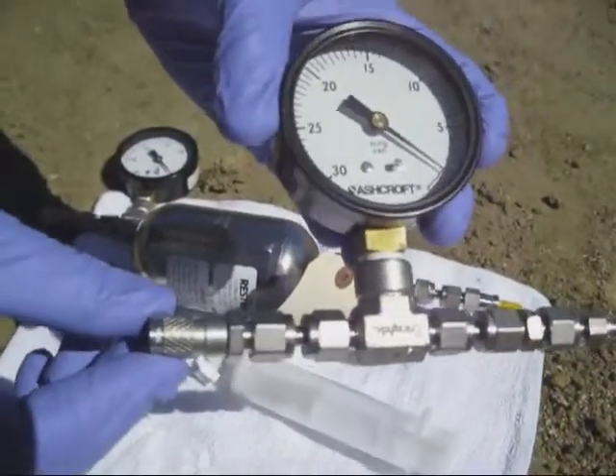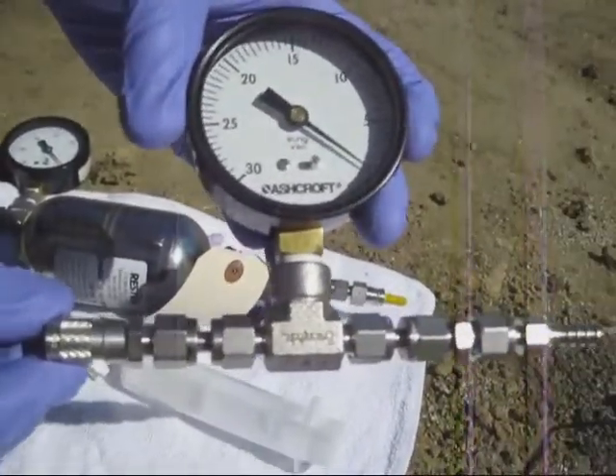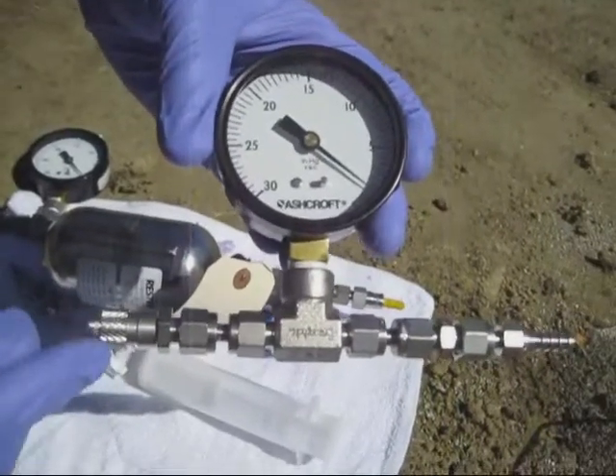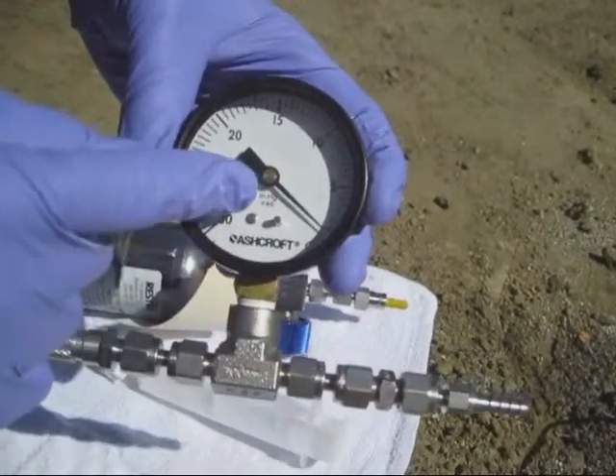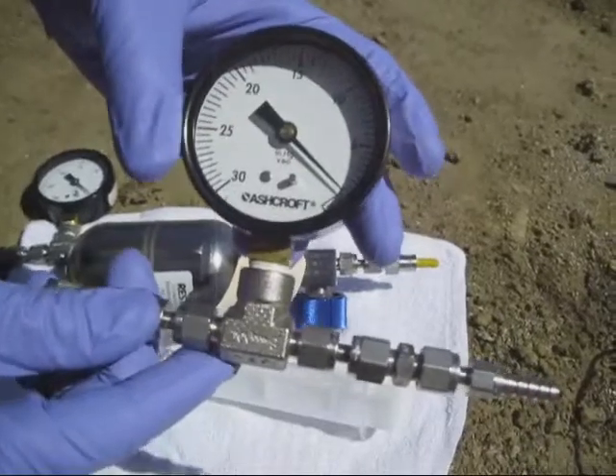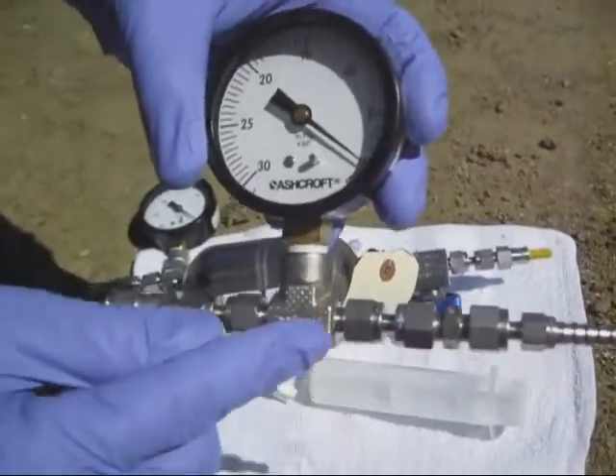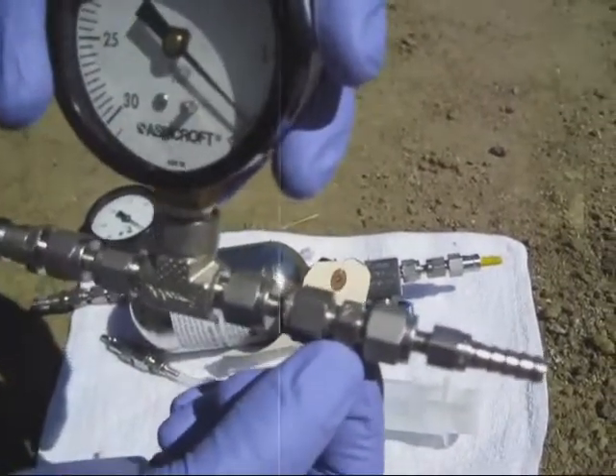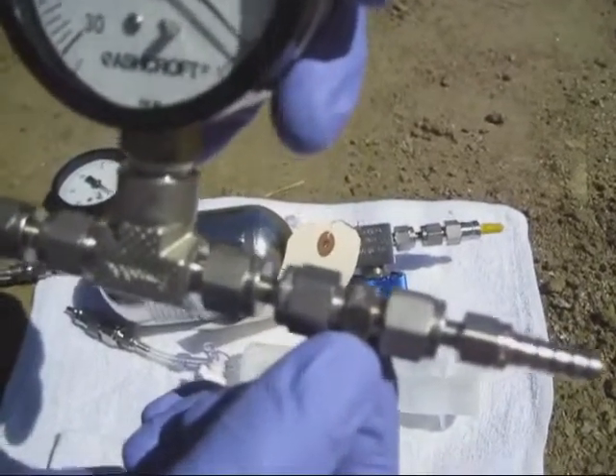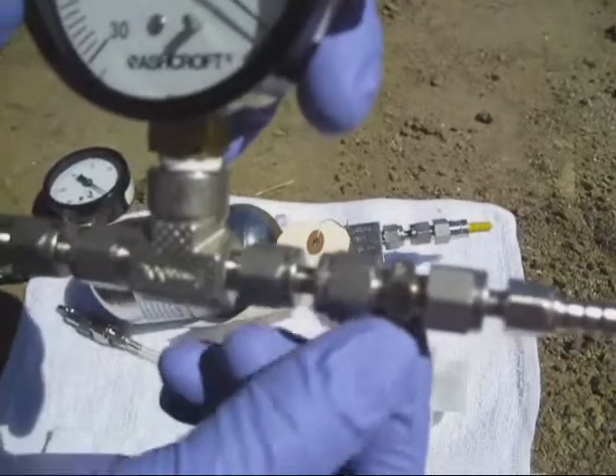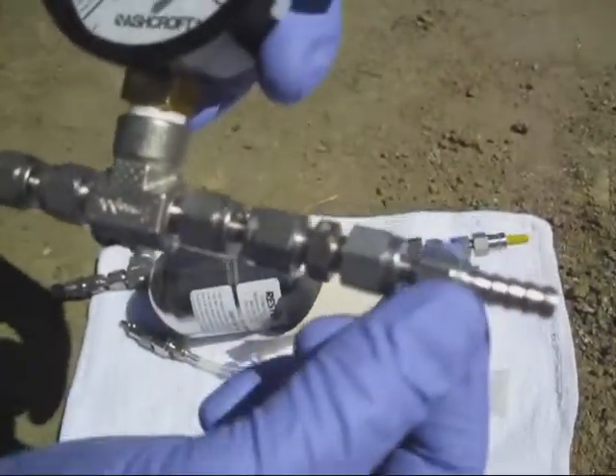On one end it's got a female quick connect connection, which is going to be connected onto our Summa canister. It goes off into a T with our vacuum gauge, which reads in inches of mercury. This piece is our restrictor orifice, which is going to limit the flow. These orifices allow about 150 milliliters per minute to travel through the assembly, and on the other end we've got a barb that we're going to connect to our probe.